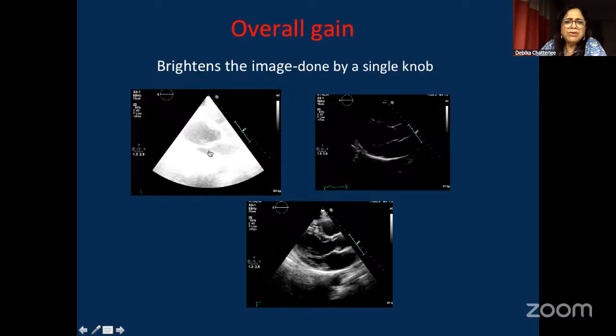So your overall gain should be such that it is optimum, neither too bright nor too dark. This overall gain is controlled by a single knob, and another gain setting is there, which is called the TGC or time gain compensation. So it is a depth-dependent gain control.